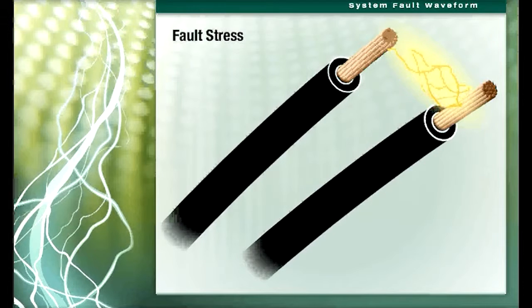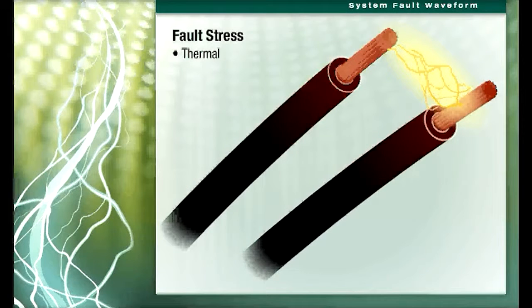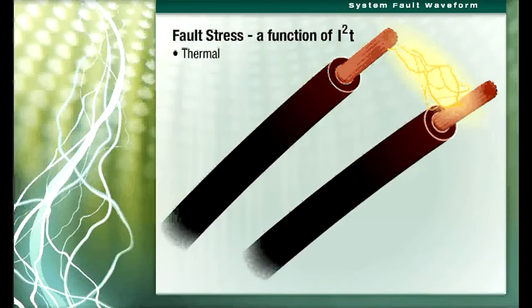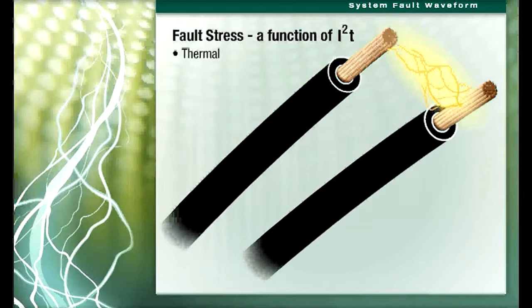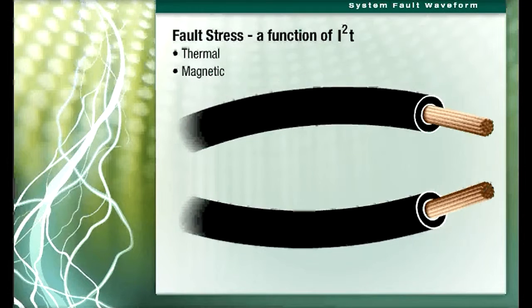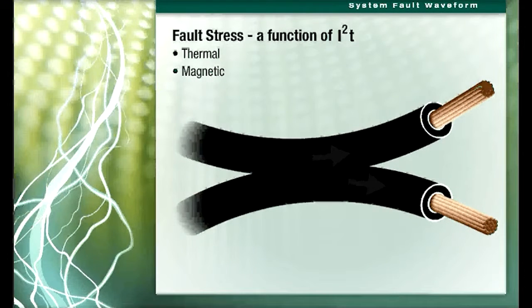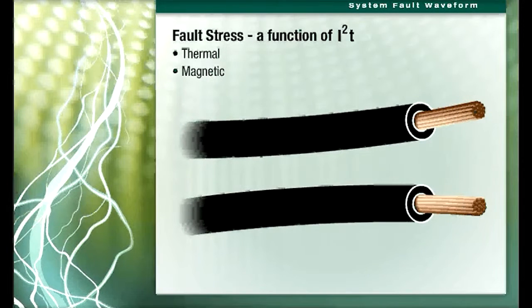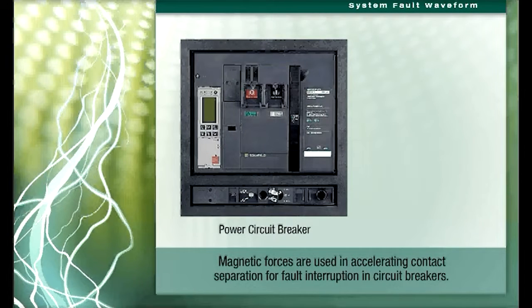Fault currents impose two stresses on electric power systems. The first is thermal: the thermal effects cause heating of the conductors in the system and are the result of the square of the current and the length of time that the current flows. The second stress is magnetic, also a function of the square of the current. It results in forces that tend to force parallel conductors apart for currents flowing in opposite directions, and pull conductors together for currents flowing in the same direction. In some cases the magnetic forces can be an advantage — for example, when they are used in accelerating contact separation for fault interruption in circuit breakers.